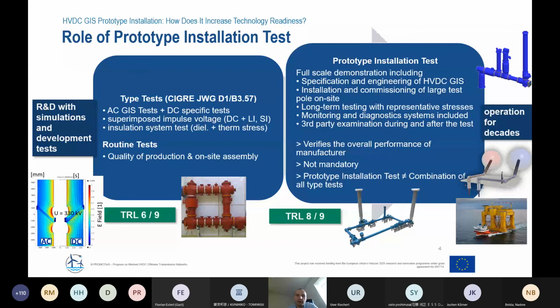And the purpose of this test is to verify the overall performance of a manufacturer to be able to deliver an HVDC GIS of the investigated voltage level. It is not a mandatory test like a type test. So it's also not to be repeated when you have a small design change in the technology or in the product. And what we should also keep in mind, and I think that also came out from Nadu's presentation of the steps in the test, is that the prototype installation test is not a combination of all the type tests, not a combination of all the worst cases. Rather, it is a simulation of real in-service conditions that are, of course, somewhat harsher than normal operation because it cannot run for 40 years, so we have a bit of increased voltage. But it should be typical for real in-service stresses or for combined stresses.